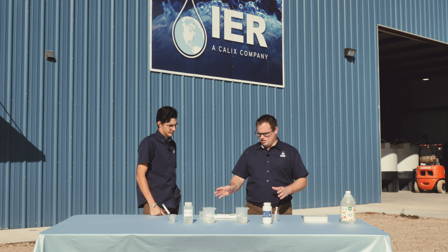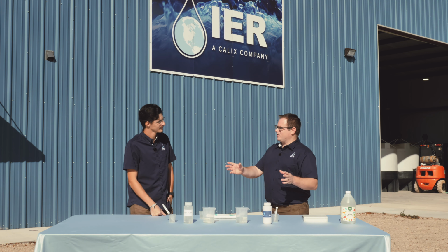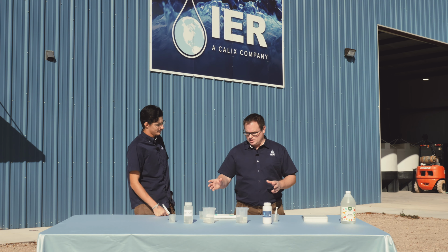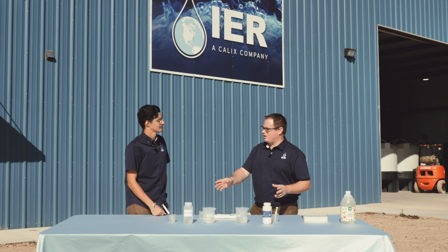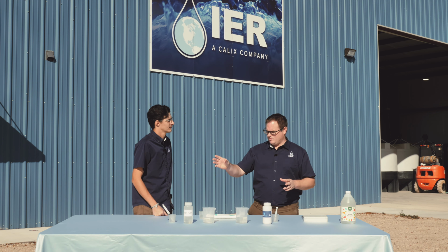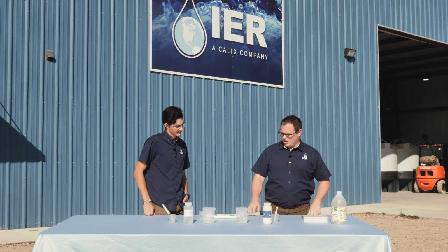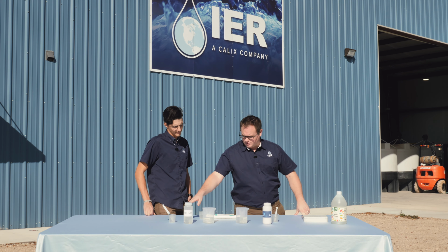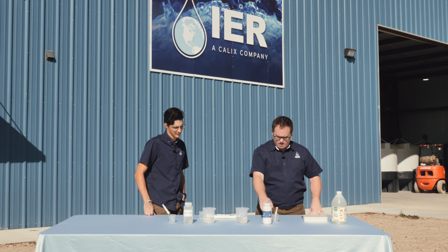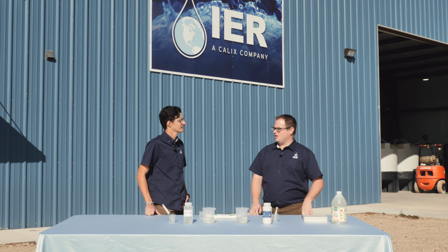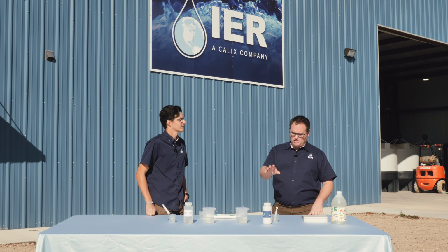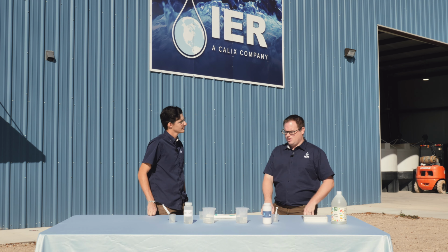As I mentioned, Dakota, we are going to run what we call the vinegar test. The main idea is we want to compare the usage rate of caustic soda to magnesium hydroxide. We start with 250 mils of just store-bought vinegar. Then we're going to add 10 mils of the 50% caustic soda, and 6 mils of the 60% magnesium hydroxide, which is ALKA-Mag Plus from IER.